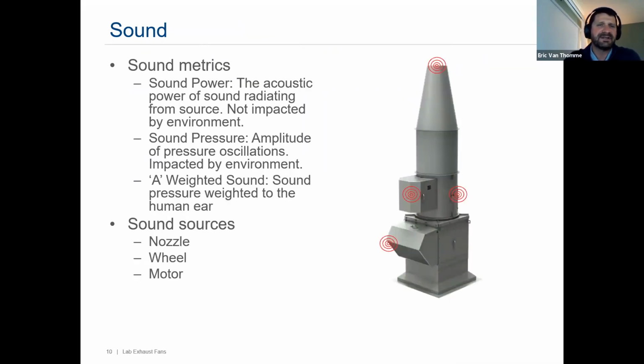You also have sound considerations. We've started to see many municipalities coming out with their own fan sound or equipment sound requirements at the property line. When you reduce the outlet area of a fan and increase the velocity, one of the drawbacks is that you're going to increase the overall fan sound. That can be an important criteria when considering which fan style, whether you're going to go with a high plume style or a regular power roof ventilator style fan.